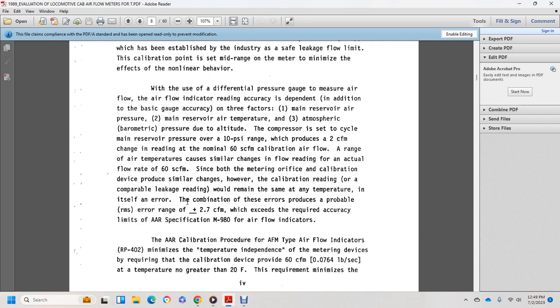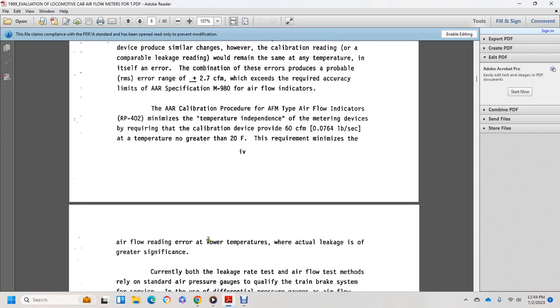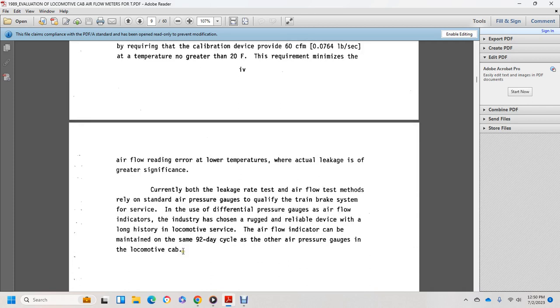The Association of American Railroads calibration procedure for the airflow method, for the type of airflow indicators RP402, means a type of temperature independence of the metering device, requiring calibration devices to be provided with 60 cubic feet a minute, or 0.0764 pounds a second. The temperature requirement of no greater than 20 degrees Fahrenheit minimizes the airflow reading error, as at low temperature the actual leakage is of greater significance.